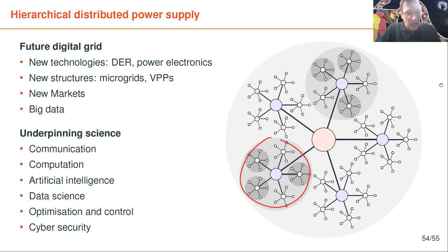As I said, currently network companies in Australia use simply blanket constraints. In a congested network, they simply say you can export 3 kilowatts per household. But that obviously is not economic, it's not optimal, because sometimes the network can take more, and there are other opportunities to use that power using peer-to-peer approaches and so on. But other approaches are emerging. The one we demonstrated on Bruny Island is one approach. Network companies here are working on operating envelopes that dynamically adjust the export limit so as to make better use of the available power. So let's go through the questions.